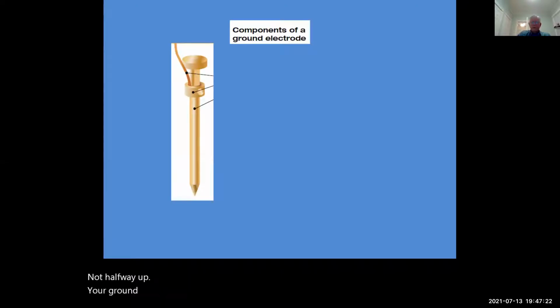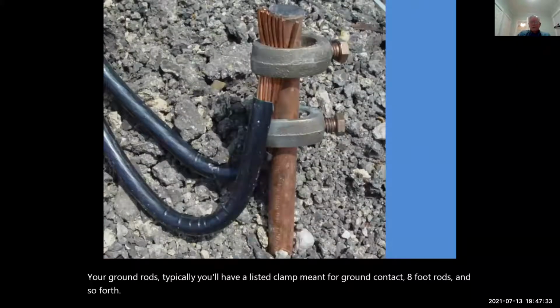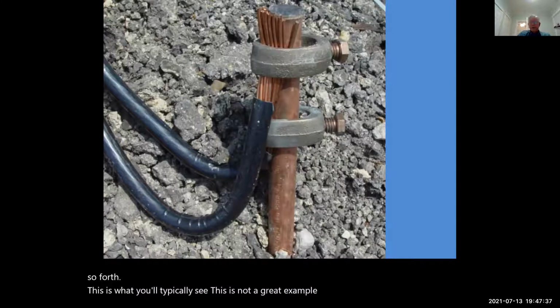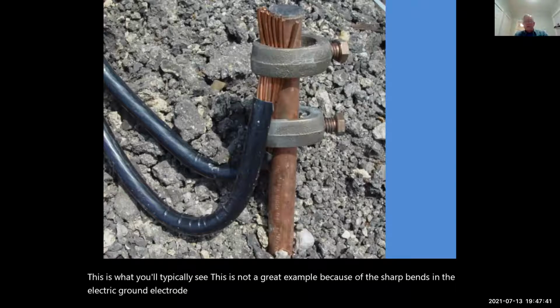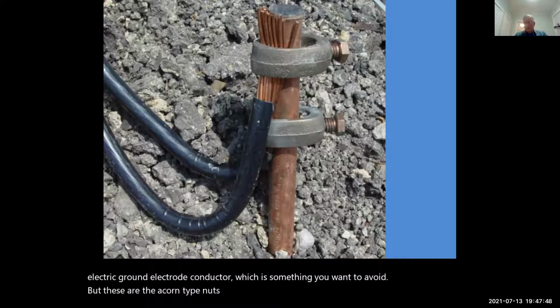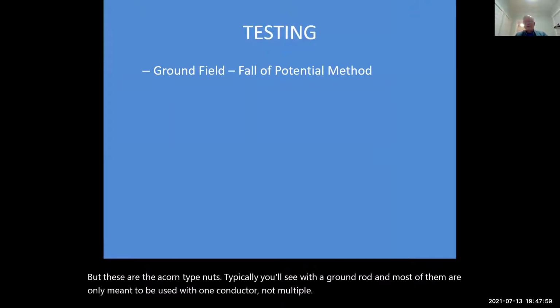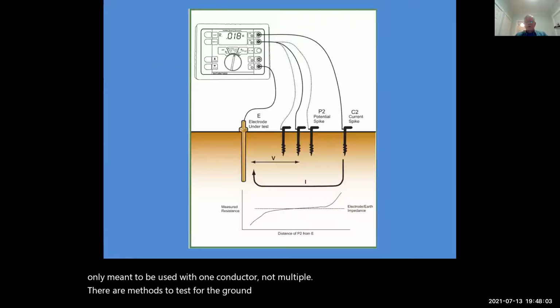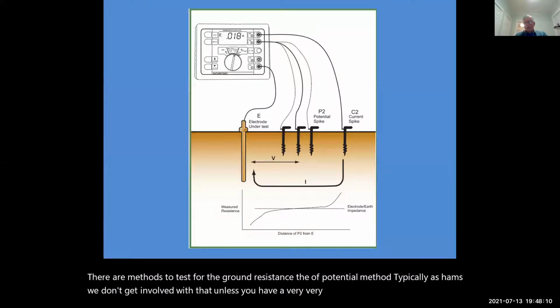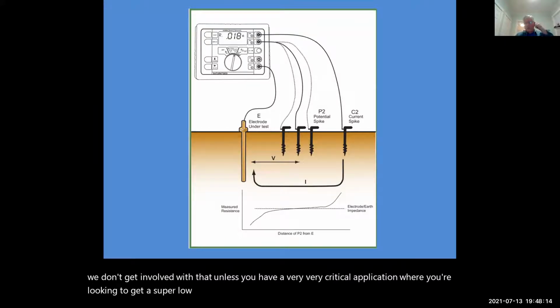Your ground rods, typically you'll have a listed clamp meant for ground contact, 8-foot rods and so forth. This is what you'll typically see. This is not a great example because of the sharp bends in the ground electrode conductor, which is something you want to avoid. But these are the acorn type nuts you'll typically see with a ground rod, and most of them are only meant to be used with one conductor, not multiple. There are methods to test for the ground resistance, the fall of potential method. Typically, as hams, we don't get involved with that unless you have a very, very critical application where you're looking to get a super low ground resistance from your ground electrode system.